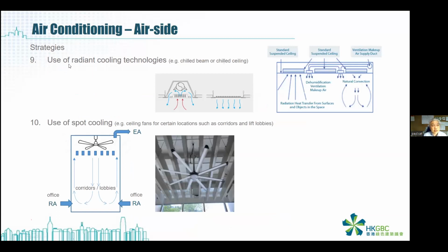Another strategy is radiant cooling technology. This kind of radiant technology is a passive system. We can use it without fan power, so it is very energy saving, or energy efficient. But the disadvantage is that the response is quite slow. In mild seasons and winter, this is very good, but in summer, this is not perfect. So in summer, we can use the primary air as the cooling medium, but in mild seasons and winters, we can use radiant cooling.